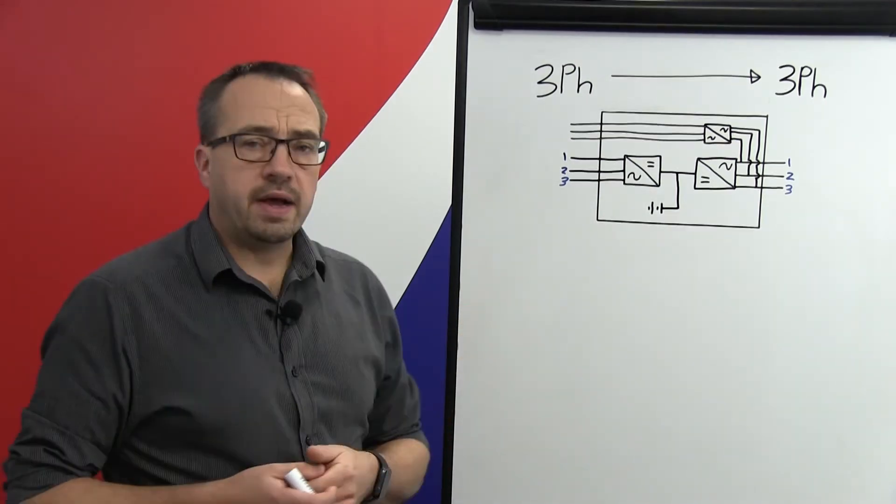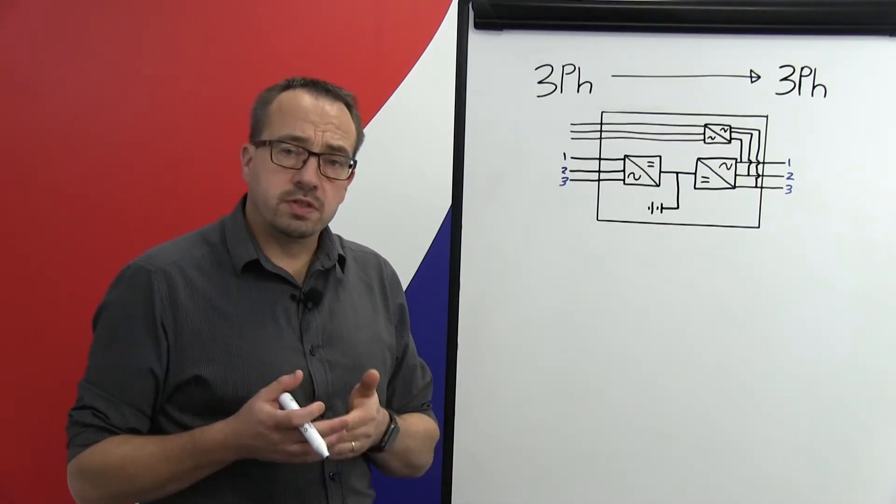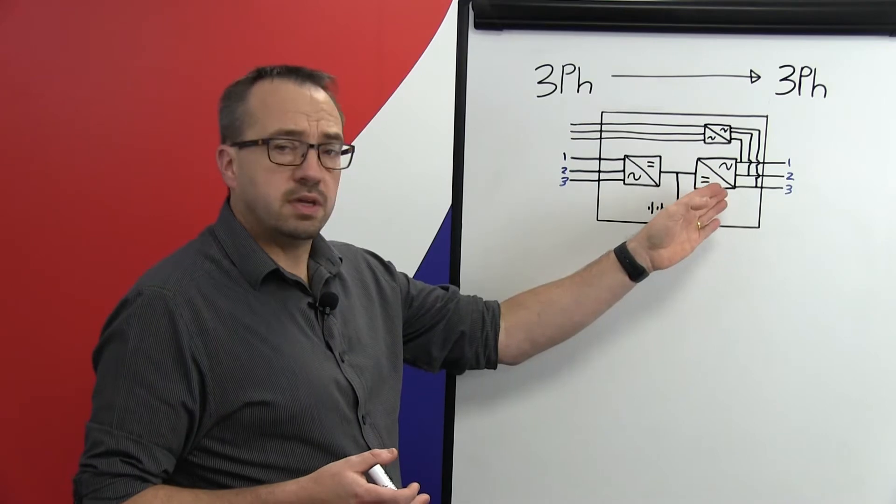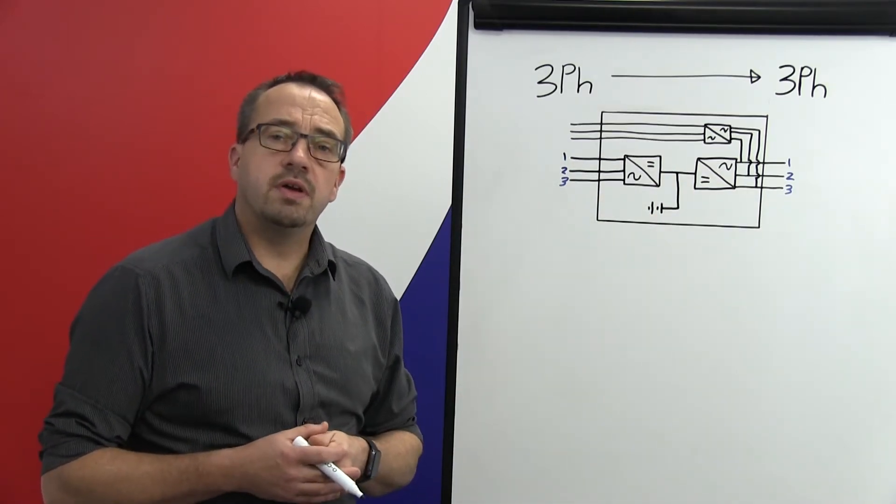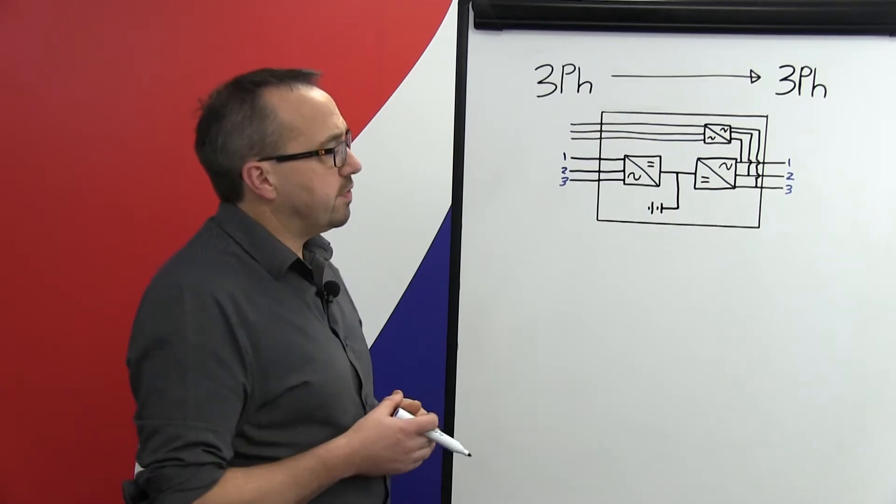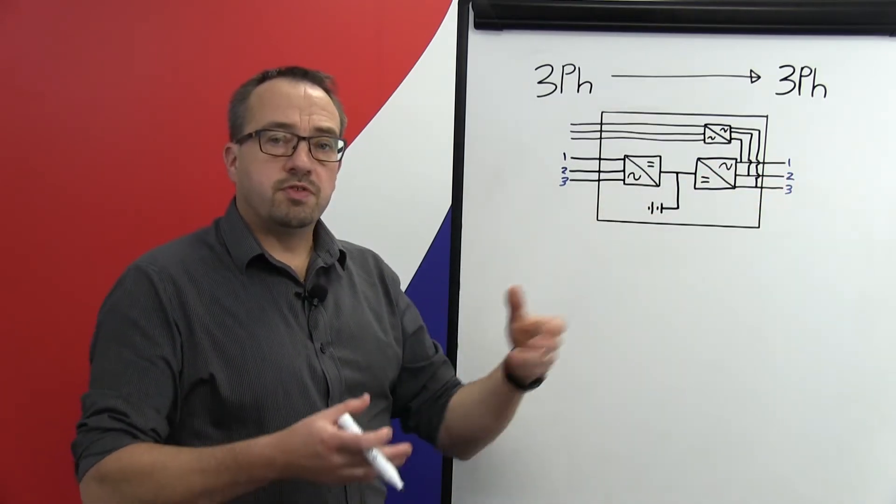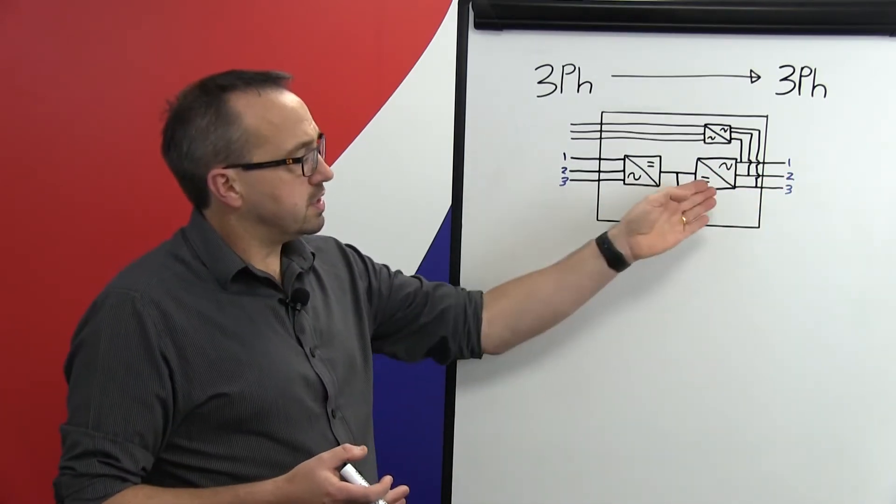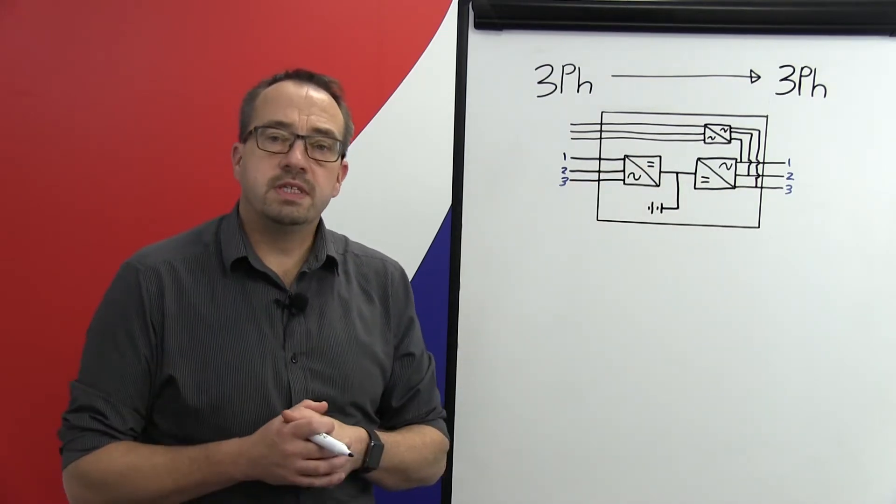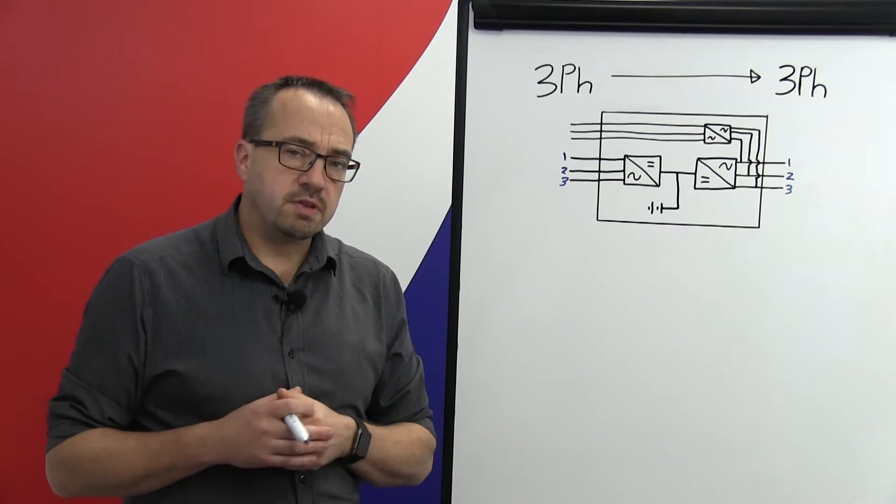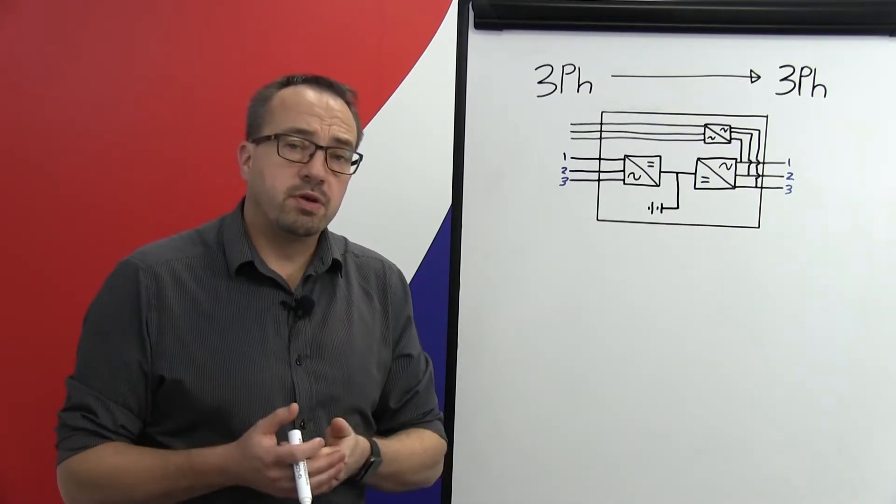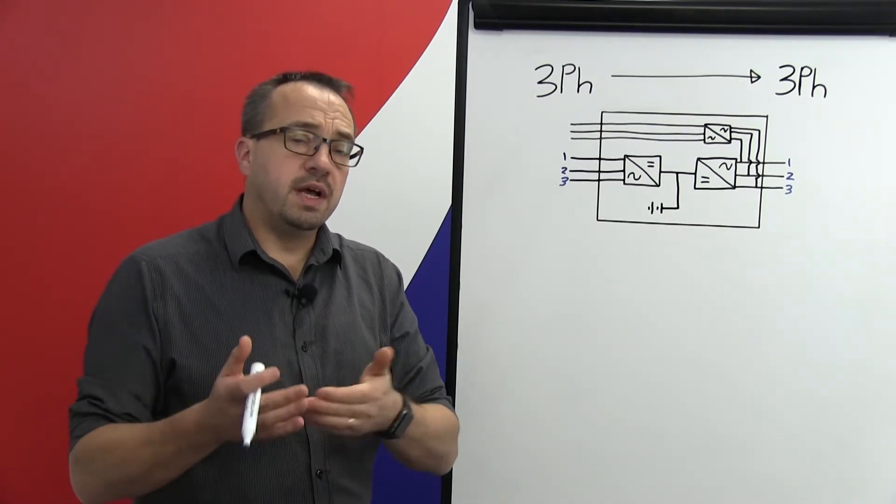Now the term online simply means that the load is being constantly supplied via the inverter and therefore should there be a break or disturbance occurring on the incoming side of the UPS system this is never seen by the connected load because during these conditions the inverter simply transfers from taking power from the rectifier to taking power from the connected batteries. Now this will occur seamlessly and hence there is never any break or disturbance to the connected load and hence the term online.